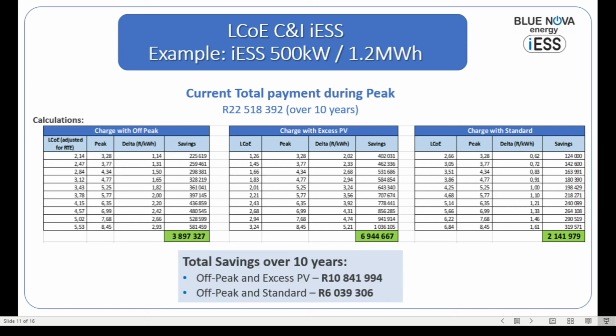So, total savings over the 10-year period, with off-peak and excess PV being used for charging, is 10.8 million. And if you charge with off-peak and standard tariffs, which means that there's no PV involved, a total savings of roughly 6 million rand can be achieved.